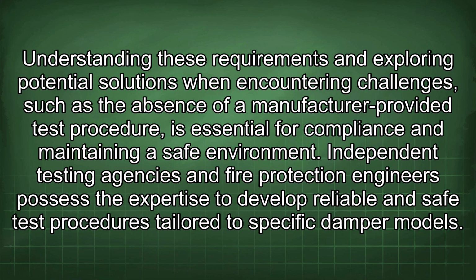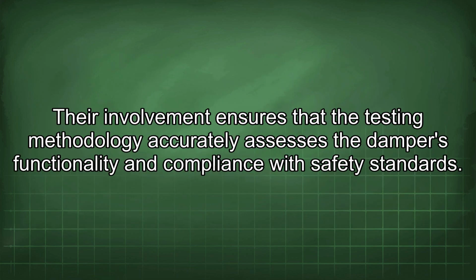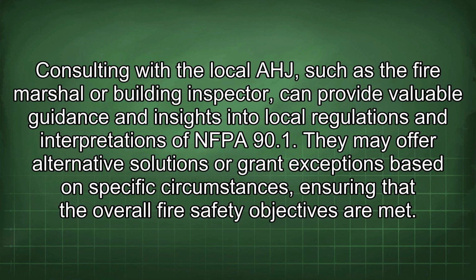Independent testing agencies and fire protection engineers possess the expertise to develop reliable and safe test procedures tailored to specific damper models. Their involvement ensures that the testing methodology accurately assesses the damper's functionality in compliance with safety standards. Consulting with the local AHJ, such as the fire marshal or building inspector, can provide valuable guidance and insights into local regulations and interpretations of NFPA 90A.